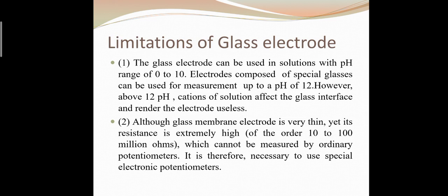However, above pH 12, cations of the solution affect the glass interface and render the electrode useless.